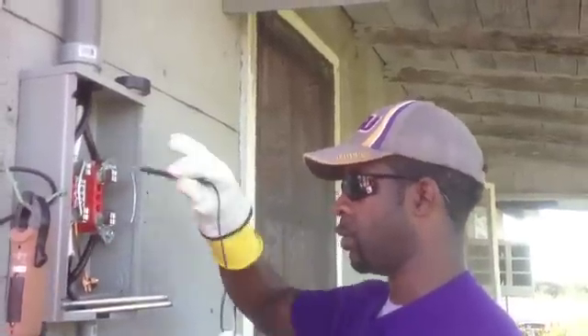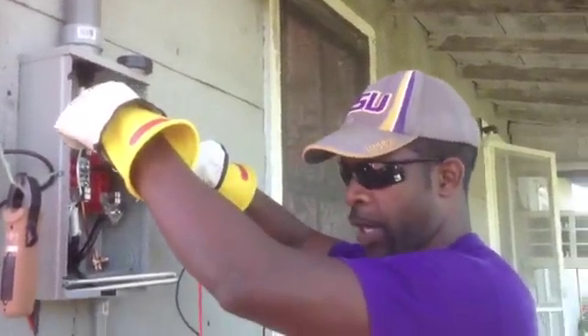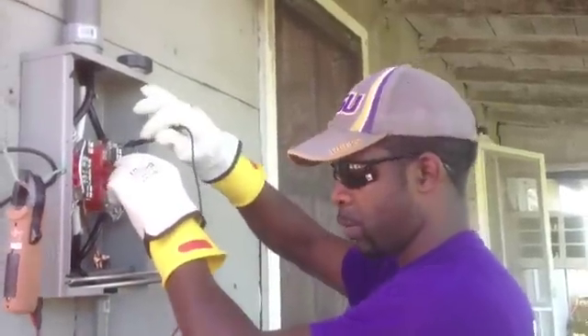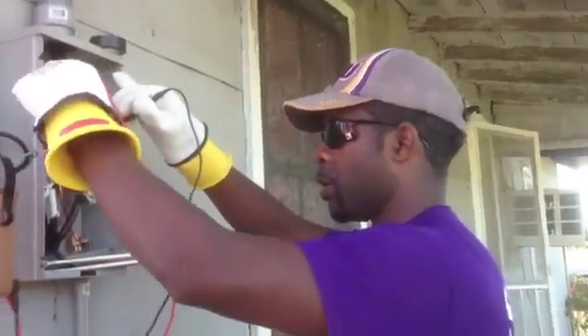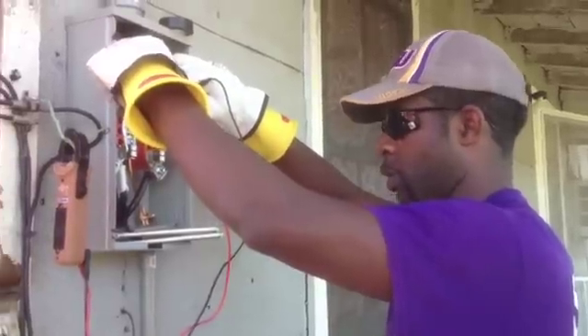Neutral to hot, neutral to hot — I got 124 volts. Other neutral to the second hot, I got 124 volts also. And then I'm going to check from phase to phase — 247 volts, 248.